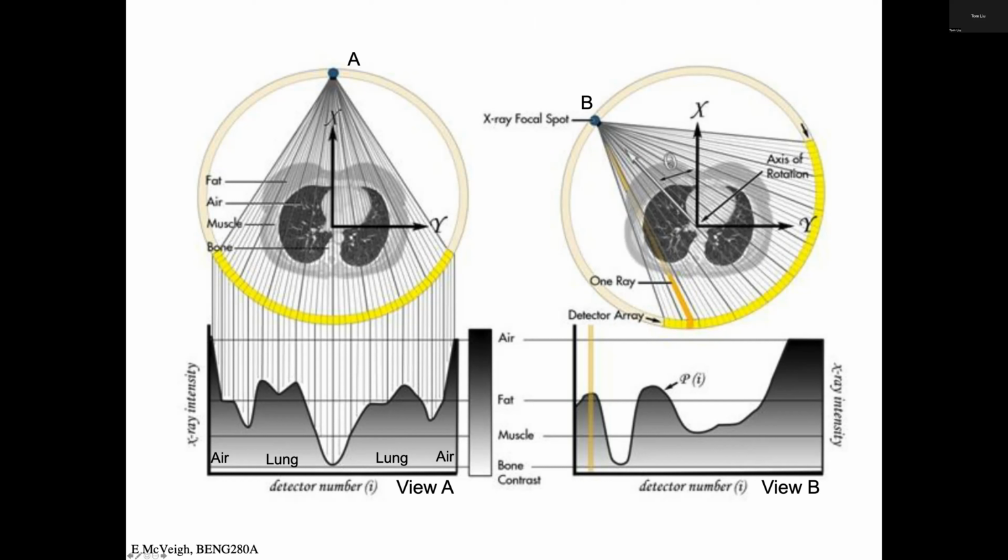So when we change the orientation of the source and the detector, remember they rotate together, and I look through here, here's the spine. It's now hitting this detector element, so that minimum moves over to here. And over here, our beam is actually missing the patient altogether. So it gives you as many X-rays as you're going to get. This is like I0, the intensity that came out of the tube hitting your detector, other than those that got absorbed by the anti-scatter grid.